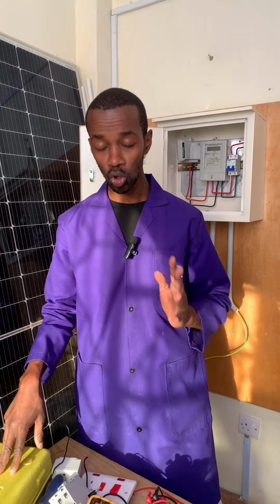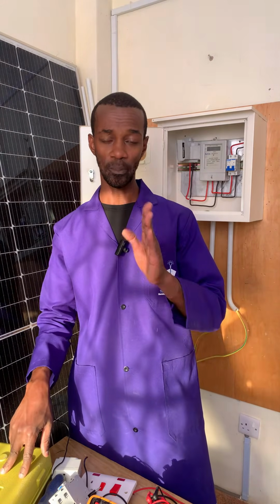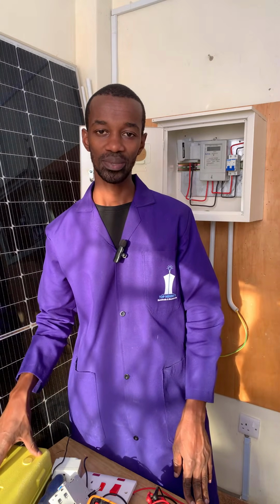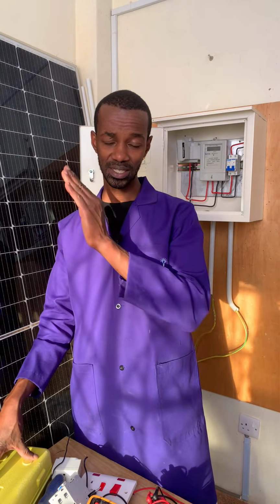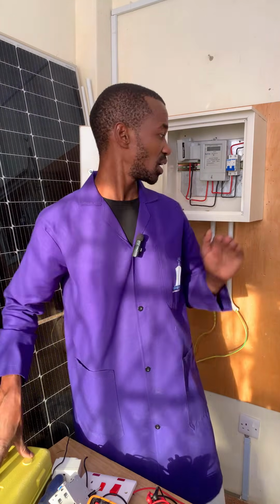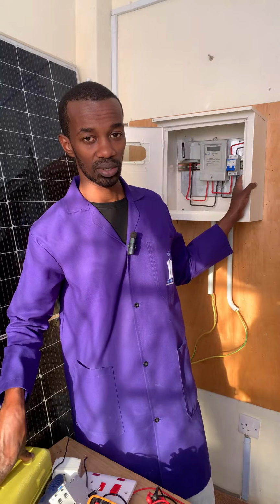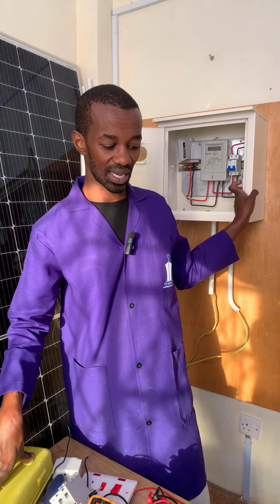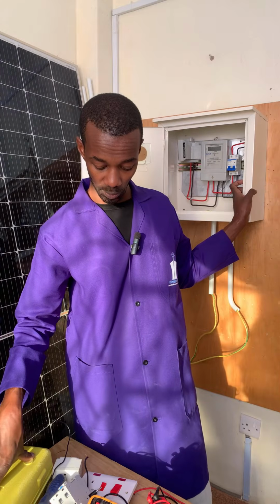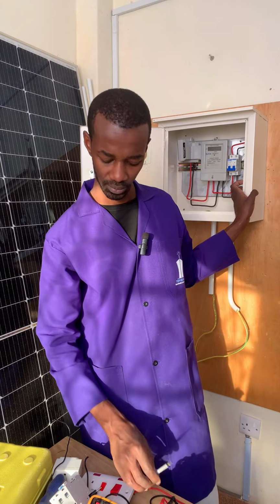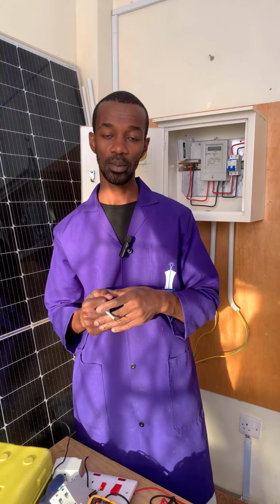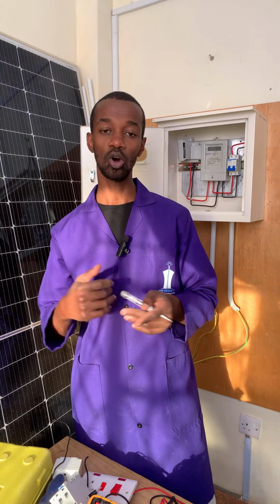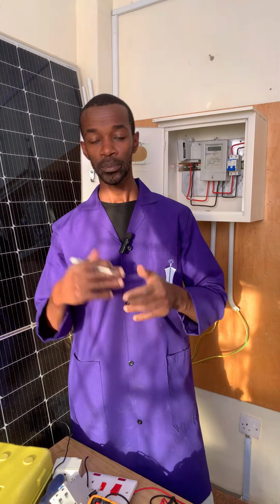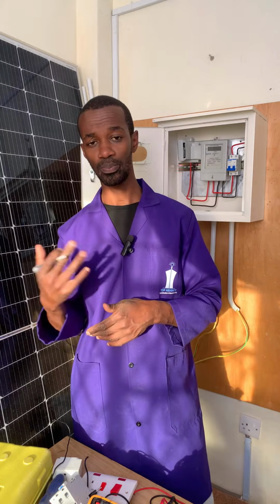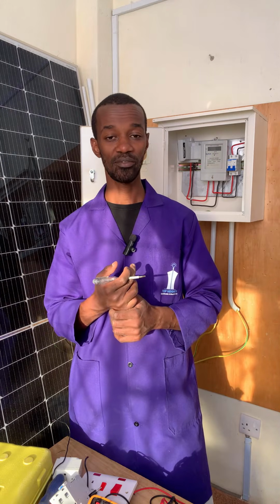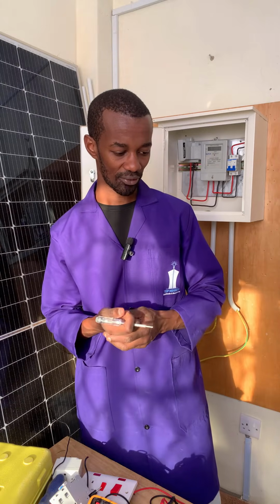But always check for that if the customer is complaining. Those are basically what you need to check. Once the specific lighting points have been checked, check the consumer unit, check the meter box. Apart from that, other external factors beyond your control include a long distance from the source, the transformer, loose connections on the neutral or power line, or the drop cable having a joint or a loose connection. Those are factors to consider.